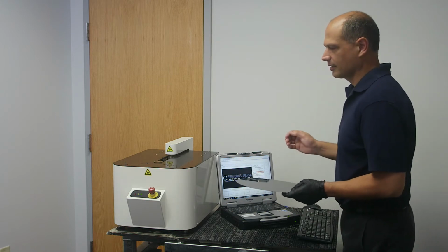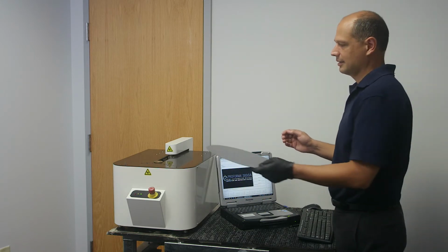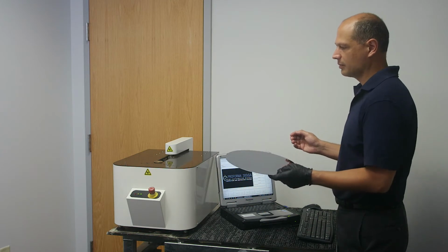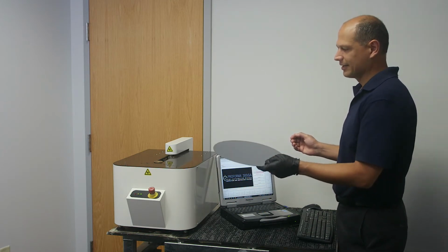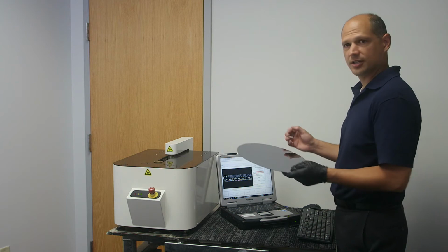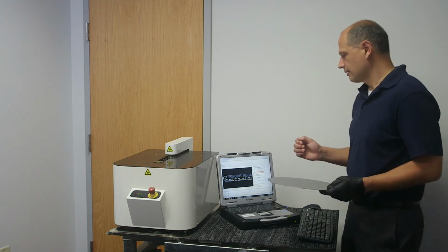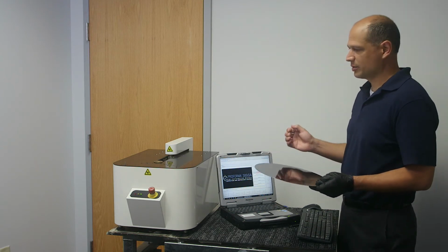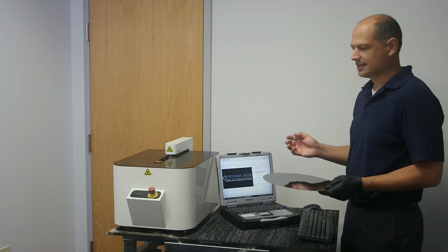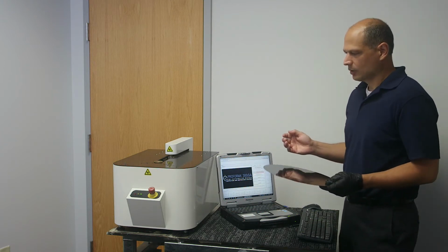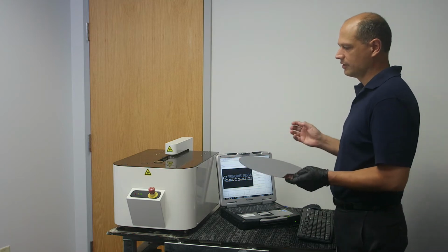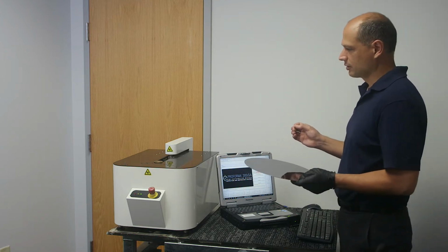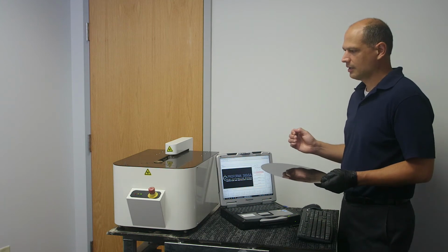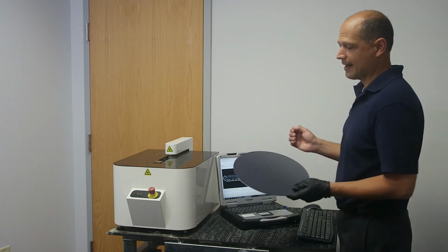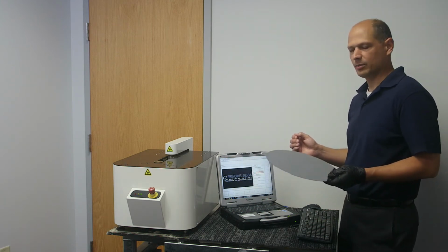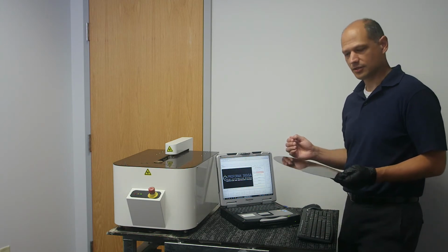The pin location is very critical to make sure that the machine is not going to try to measure a smaller wafer having a larger one on top. It could crush it. The first thing we're going to do, and this should be done roughly every day, is calibration. We're going to use a wafer of known thickness in order for the machine to calibrate itself. If you wish to have a calibration pattern, we can sell those to you.